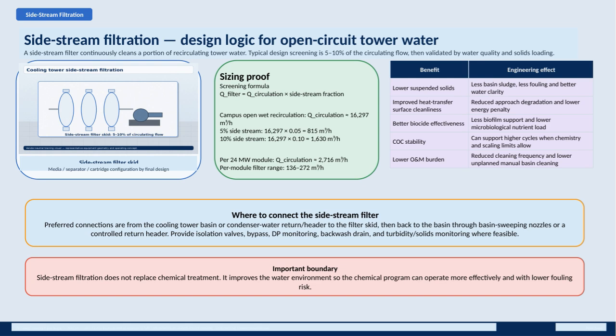The benefits of side stream filtration are significant. It reduces suspended solids, which means less sludge buildup in the basin, less fouling, and clearer water overall. This leads to cleaner heat transfer surfaces, which improves efficiency by reducing approach temperature degradation and lowering the associated energy penalty. Additionally, a cleaner system makes biocides more effective and limits biofilm formation, as well as microbiological nutrient load.